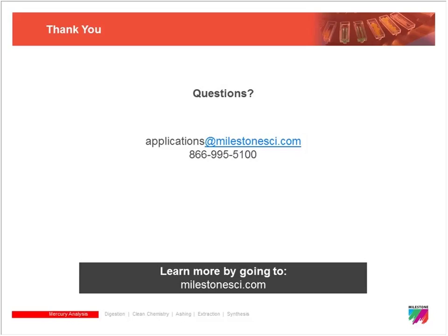So there's a question if the DMA requires a special clean room or can it be placed in a regular room where other trace metals are analyzed. So you do not need to place the DMA in a clean room, as this kind of goes back to the machine blanking. So when you're running your machine blanks, your carrier gas will have any background levels of mercury analyzed as part of the blank. So you don't need to run the system in a clean room, and you're only analyzing for mercury itself. So any other contaminants would be trapped inside the catalyst.